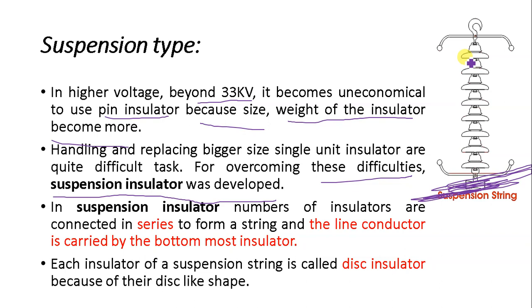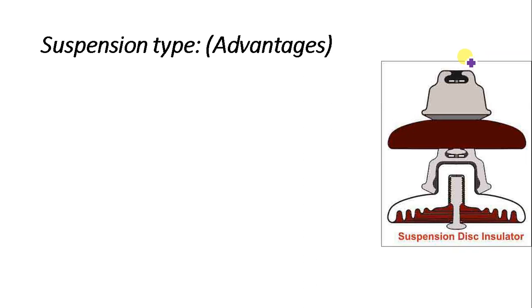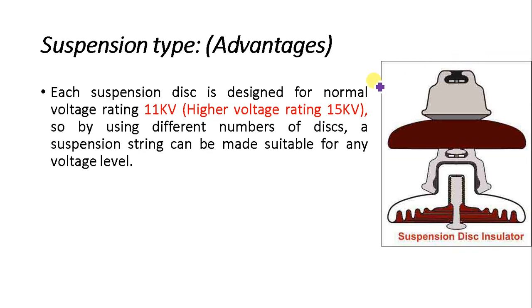Let us now discuss the advantages of suspension type insulators. Each suspension disc is designed for a normal voltage rating of about 11 kV, or up to 15 kV for higher rating discs. By using different numbers of discs, a suspension string can be made suitable for any voltage level. This flexibility is a major advantage over pin type insulators.